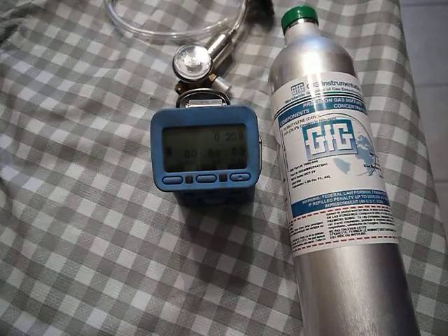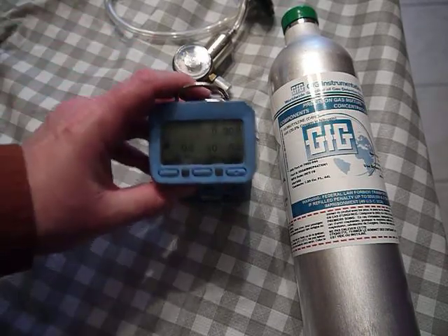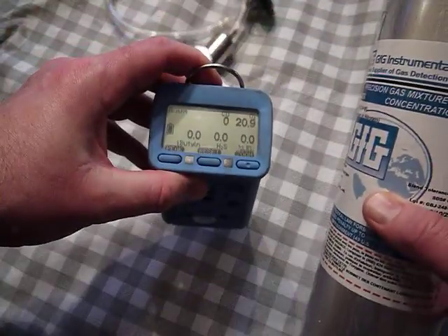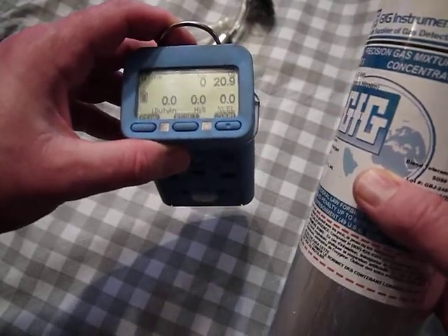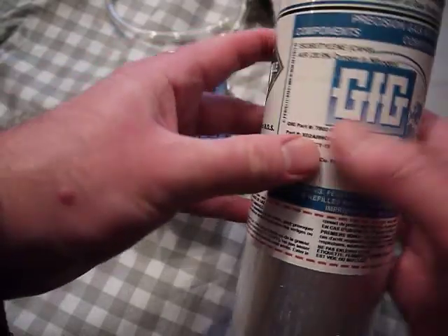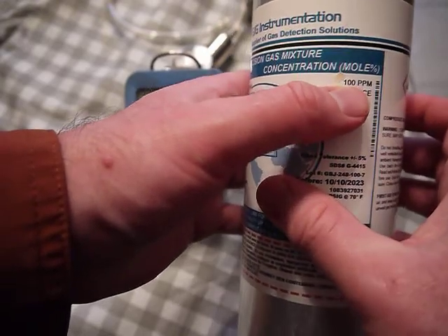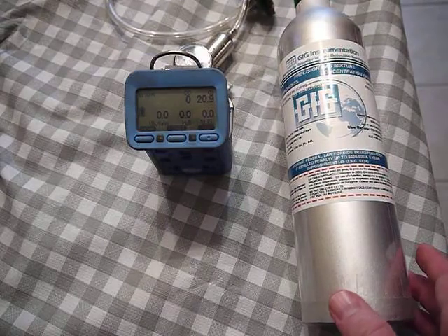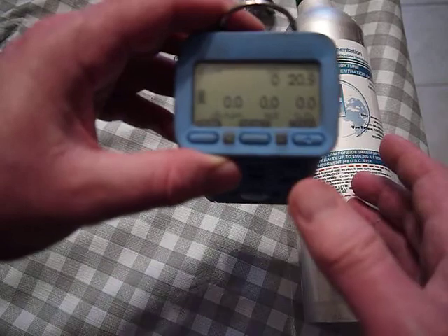Sometimes we'll receive gas detectors that will have different alarm points or calibration values than what's required. This is just an example, but this gas detector has an isobutylene sensor installed, and I know that in this case it's set to 200 ppm, and I'm looking at my calibration gas for isobutylene, and it's 100 ppm. So this would apply to many other sensors, for example, HCN like hydrogen cyanide, or even different values for carbon monoxide and stuff like that.